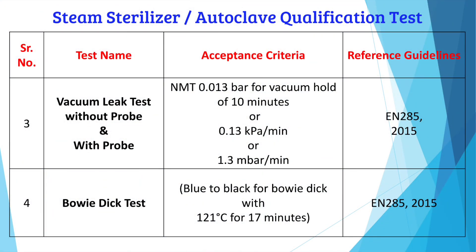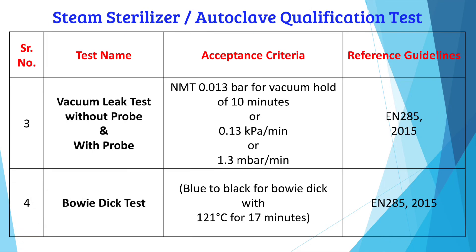The next test is the vacuum leak test, performed both without probe and with probe. The acceptance criteria is not more than 0.013 bar for a vacuum hold of 10 minutes, or 0.13 kPa per minute, or 1.3 mbar per minute. This is given in EN 285:2015.